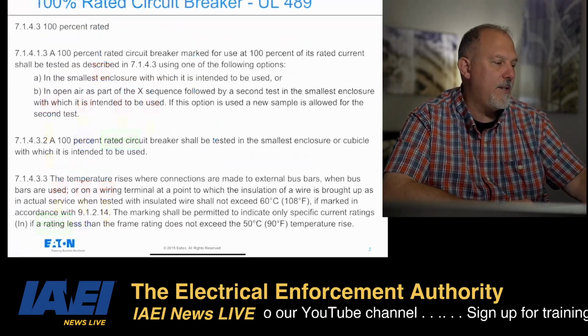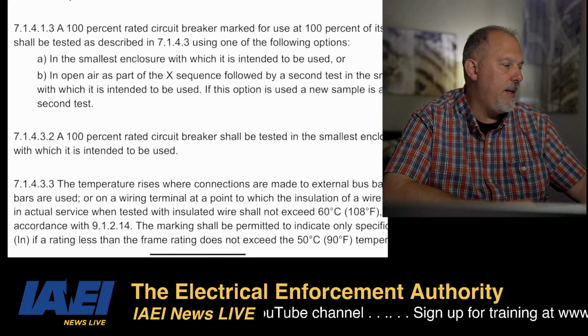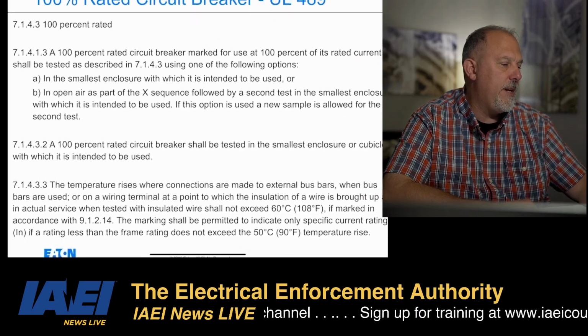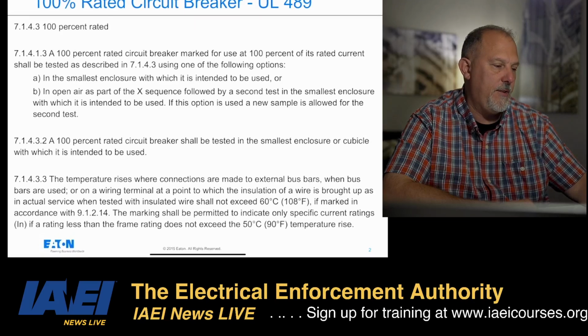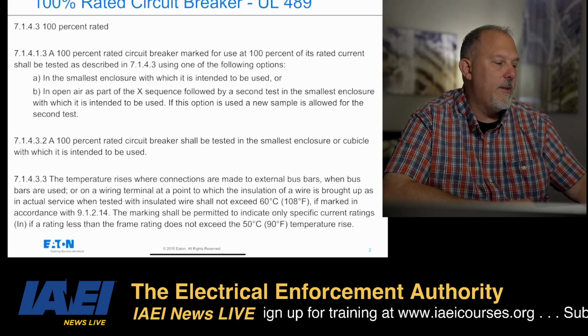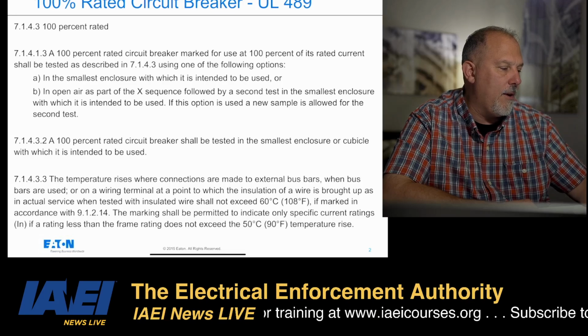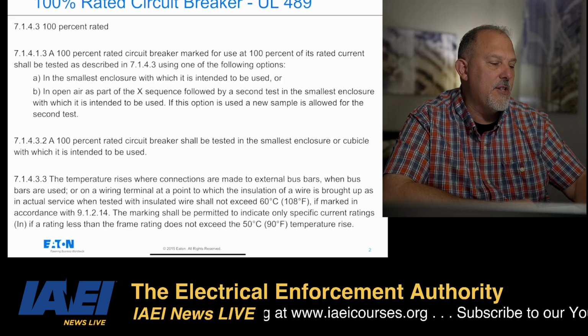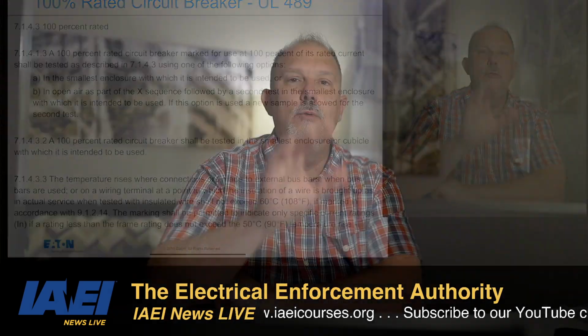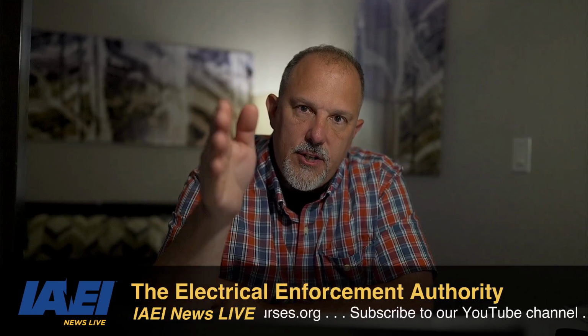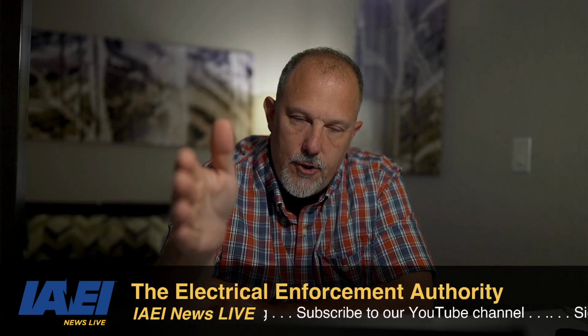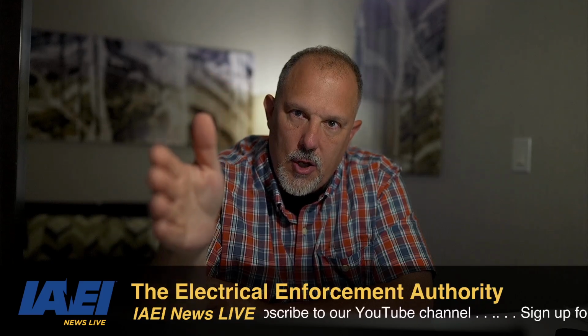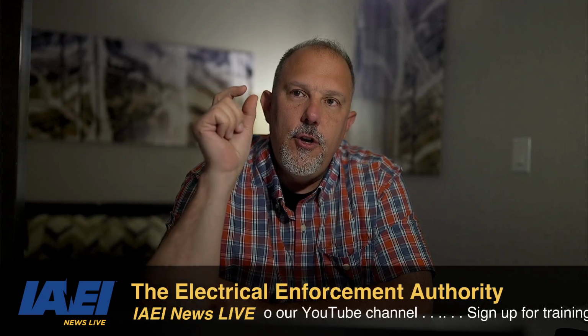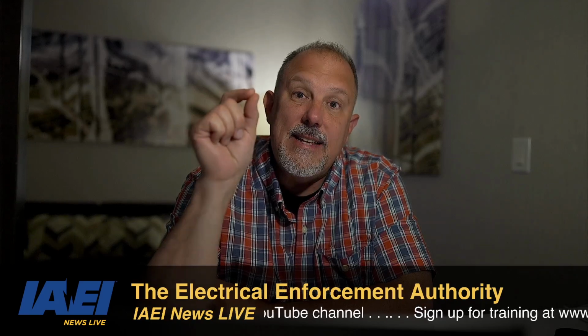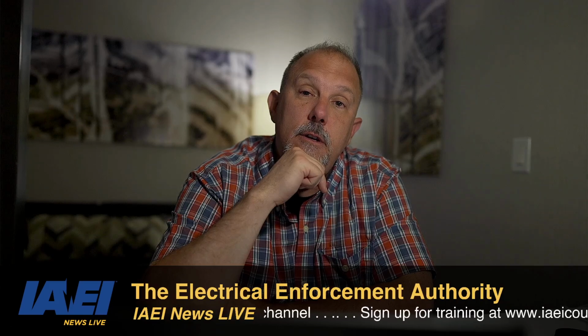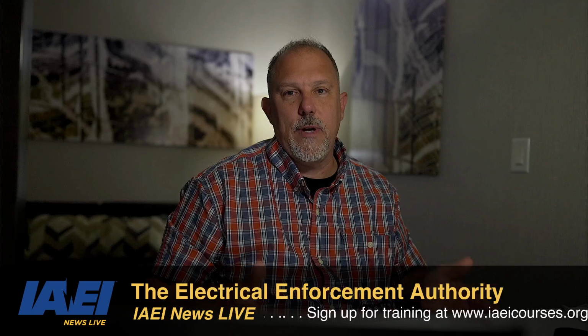Why is that? Why, Tom? So here's out of UL 489: a 100% rated circuit breaker marked for use at 100% of its rated current shall be tested as described in the smallest enclosure in open air. So a 100% rated breaker shall be tested in the smallest enclosure or cubicle within which it is used. So when you have a 100% rated circuit breaker, it's not about the circuit breaker alone. It's, I would argue, more about the assembly than it is about the circuit breaker, because you have to maintain a temperature rise when it's in its enclosure.